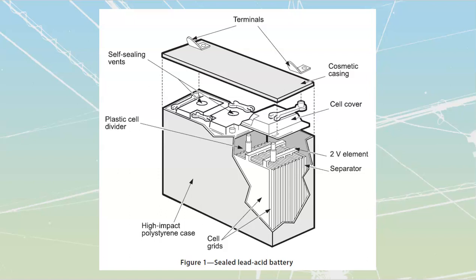That being said, if you have a piece of unit equipment, the charger inside of that is going to be built for the type of battery. If it's designed for lead-acid batteries, we can only recharge lead-acid batteries. If it's designed for Nicad, we can only recharge Nicad. And if it's designed for lithium-ion, we can only recharge lithium-ion. So in some cases, you will still need to acquire some of those Nicad batteries.